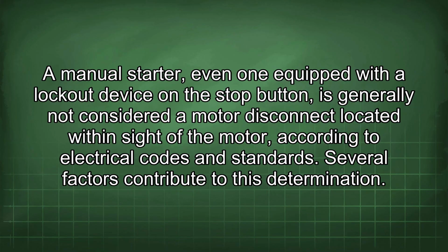A manual starter, even one equipped with a lockout device on the stop button, is generally not considered a motor disconnect located within sight of the motor, according to electrical codes and standards. Several factors contribute to this determination.